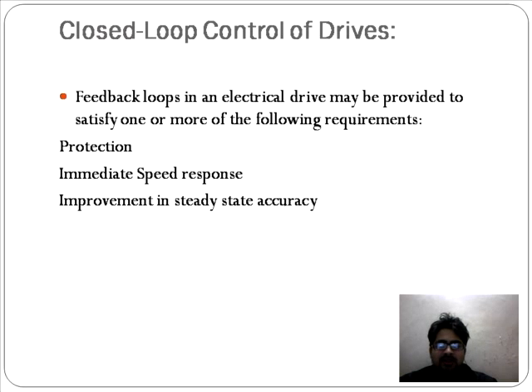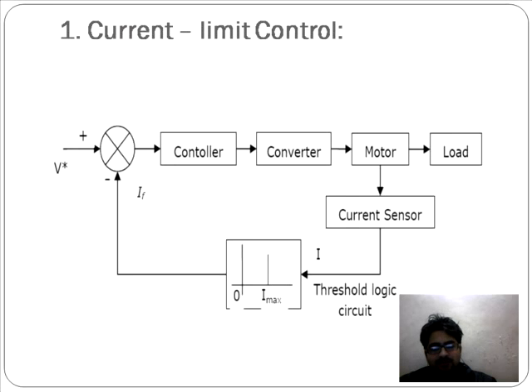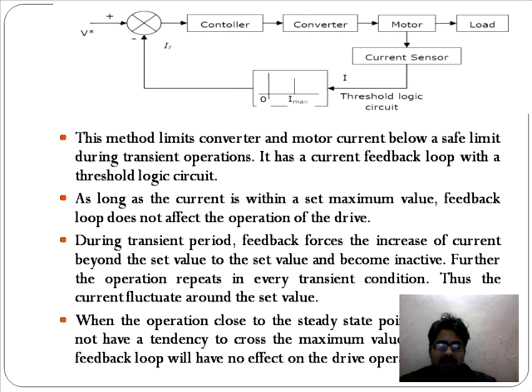There are a few schemes we are going to cover in this lecture on closed loop control drives. The first scheme is current limit control. This current limit control scheme limits the converter and motor current below a safe limit during transient operation — basically during starting, braking, acceleration, and deceleration. It uses a current feedback loop with threshold logic circuitry.